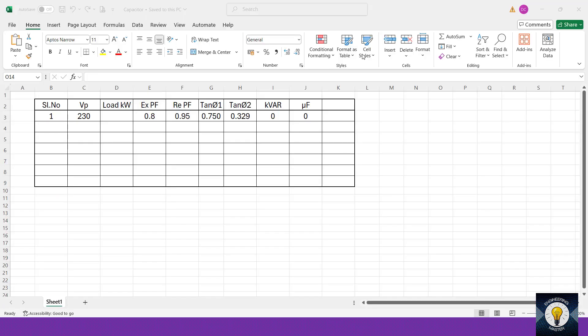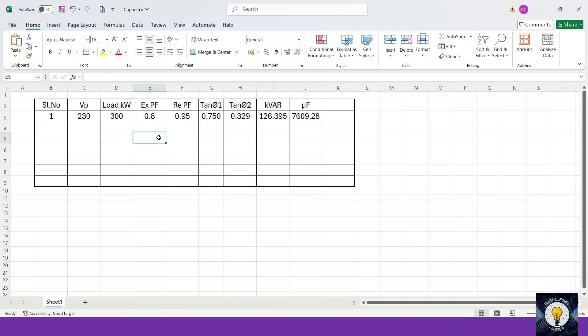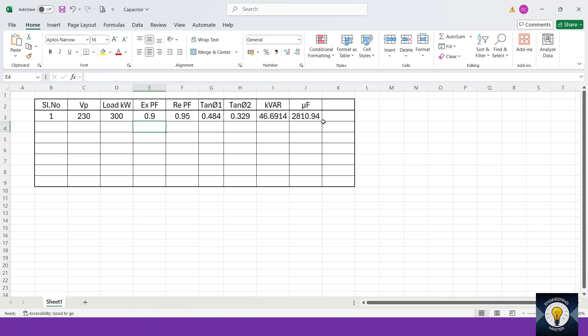To make the calculation easier, I have prepared an Excel sheet for you. In that sheet, phase voltage is specified as 230 V — you can change it if your phase voltage is different. Enter the load in kilowatt, existing power factor as 0.8, and required power factor as 0.95. You will get the kVAR and microfarad values automatically. If you change the existing power factor, all values update automatically. The download link is in the description.